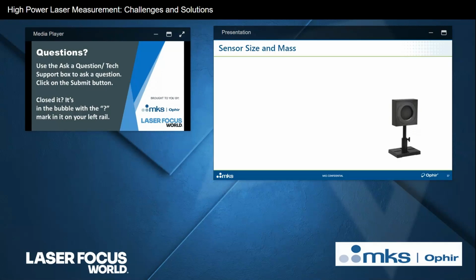So at Ophir, we have a trick that we developed. I assume that some of the manufacturers might have something similar, but whereby we can use small sensors that normally are meant for much lower powers to measure high power beams without having to be huge and bulky and whatever. How do we do this? So there are some tricks that we employ to be able to measure high power lasers without needing large, heavy, expensive water-cooled equipment. And this involves what at Ophir, at least, we call pulsed power mode.